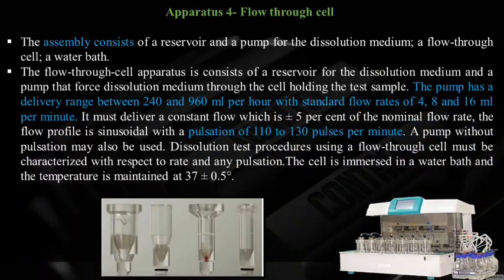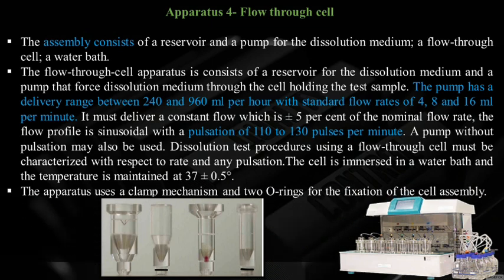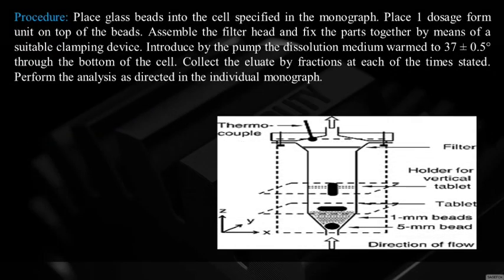Apparatus 4 — Flow-Through Cell: consists of a reservoir and pump for dissolution medium, a flow-through cell, and a water bath. Four different cell types are available. The pump forces dissolution medium through the cell holding the test sample, with delivery range of 240 to 960 mL/hr and standard flow rates of 4, 8, and 16 mL/min. Flow must be constant within ±5% of nominal flow rate. Flow is sinusoidal with pulsation of 110 to 130 pulses per minute. Temperature maintained at 37 ± 0.5°C.